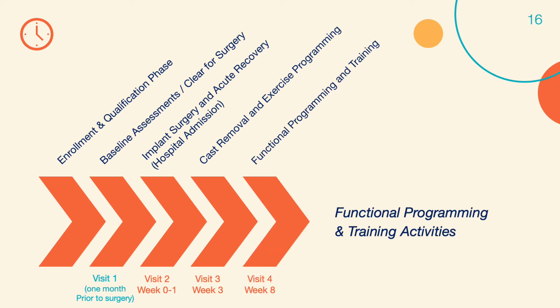Study Visit 4. The participant returns to Cleveland at approximately 8 weeks post-surgery, after about 5 weeks of exercise using the implanted system at home. The purpose of this visit is to program grasp modes to be used for functional activities and to establish myoelectric control parameters that are effective for operating the NNP. The participant will be trained in all aspects of system use. As with prior visits, Cleveland will facilitate remote or in-person participation for key aspects of the visit, as desired by the site. This visit will last approximately 1 week.